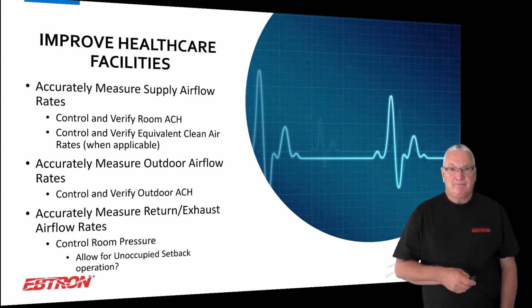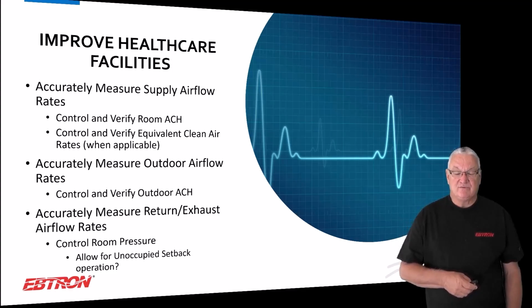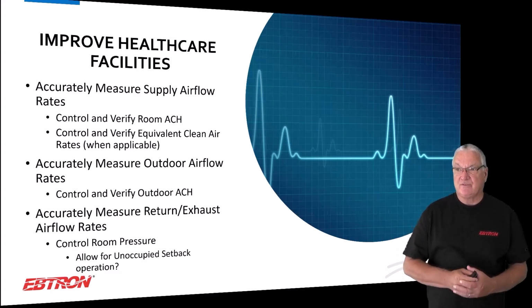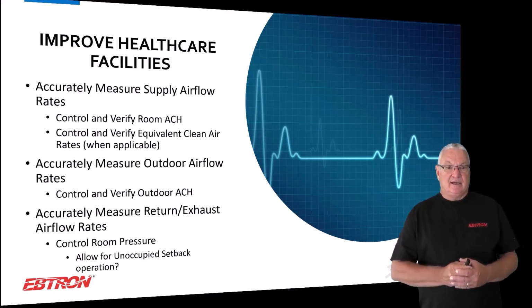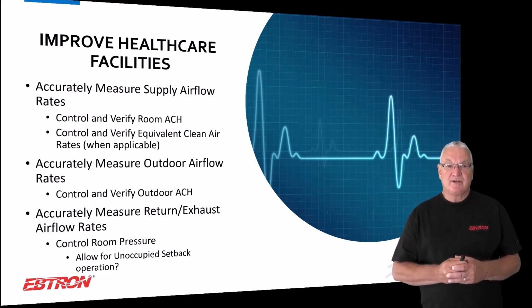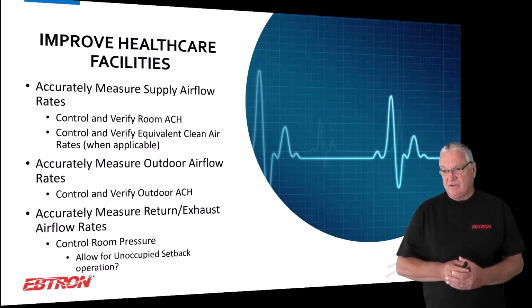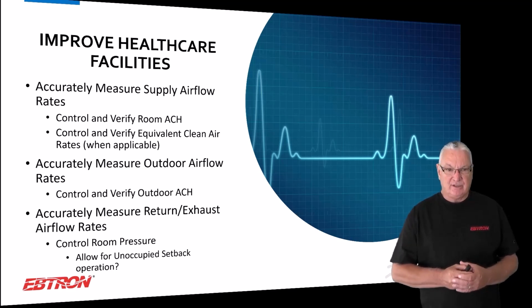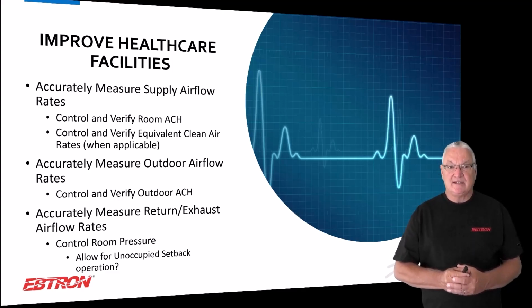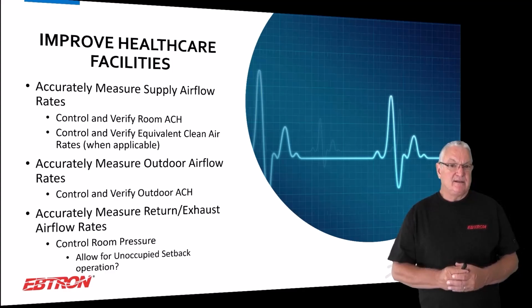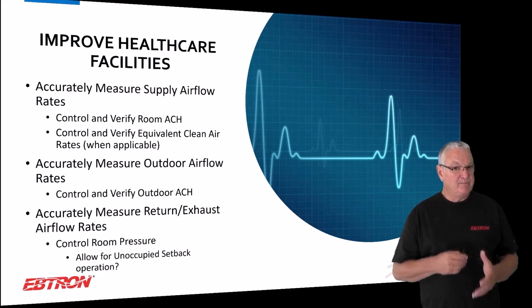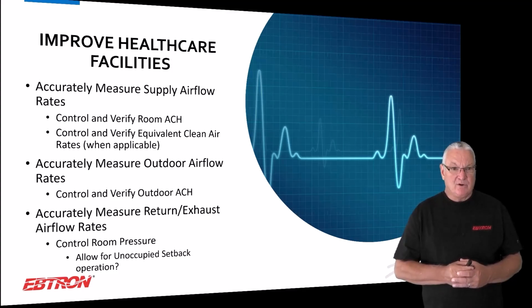And then finally, the thing that I want to talk about is room pressure control, particularly in operating rooms and spaces like that. It's really important that we do flow control. There are challenges with flow control that we're going to talk about, but that's how we want to really control room pressure. And then really we want to think about whether or not, from an energy perspective, we can actually do an unoccupied setback operation. And in my 40 years, I have not seen that work, and I have a pretty good handle on why I think it doesn't work. And so I want to talk about some things that I think we can do to make it so potentially we can go to unoccupied setback mode where it's allowed.